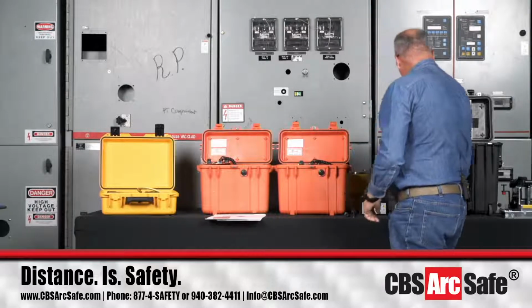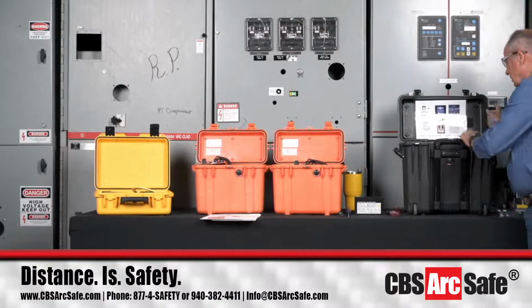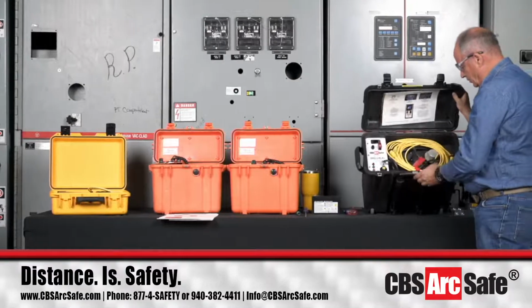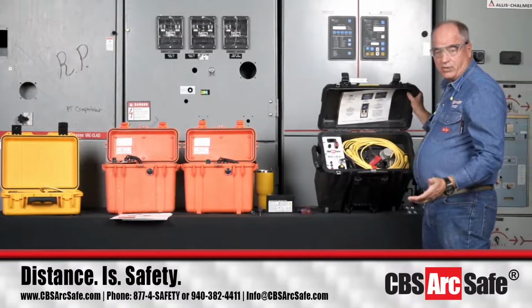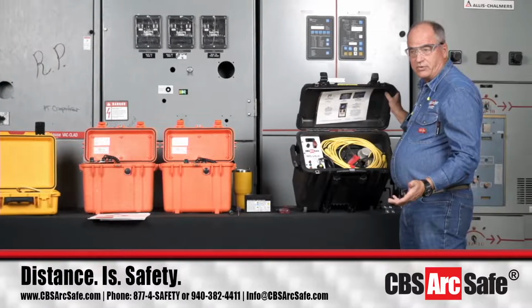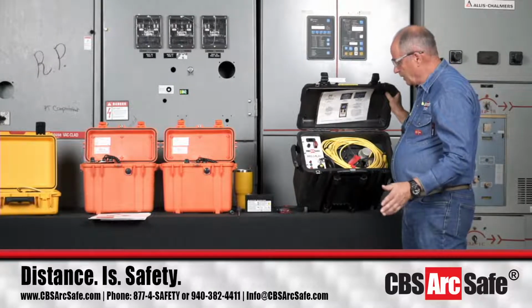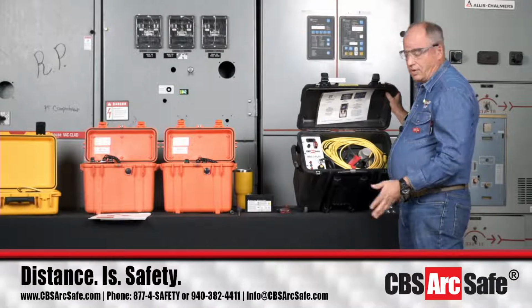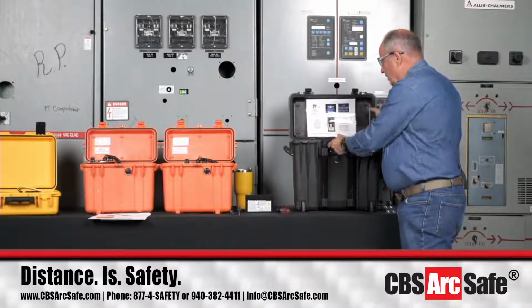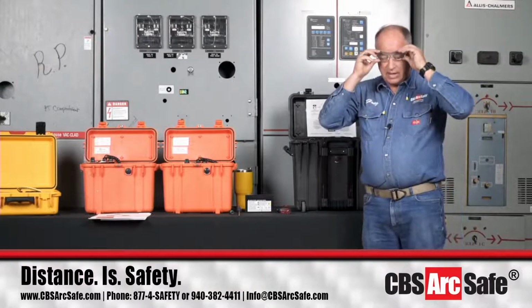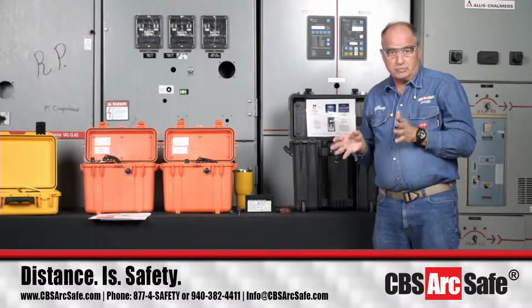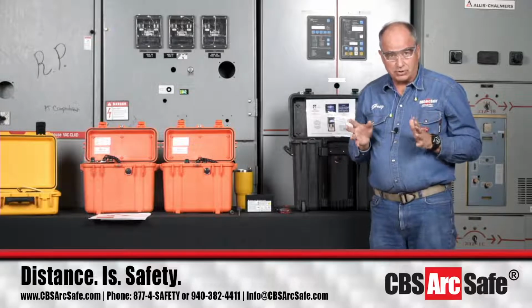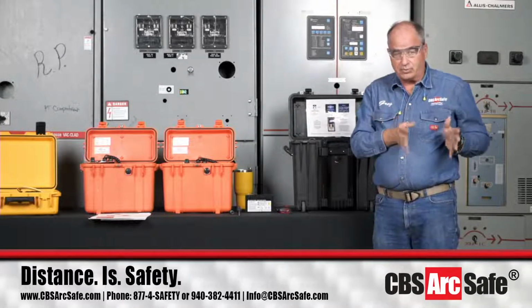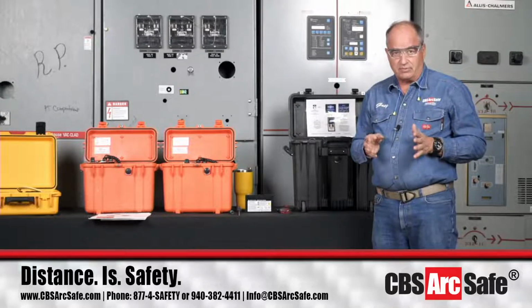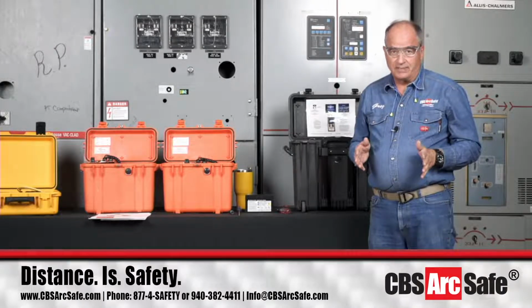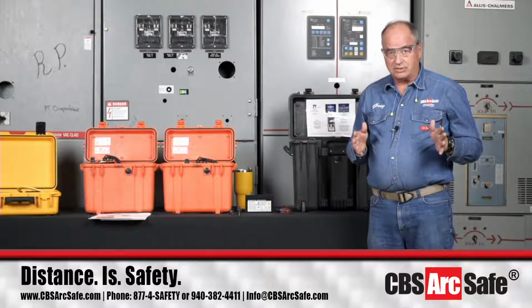With the RS3 DSR line, whether it's an RL, a DSR1, or anything else, this uses a 3.2 amp hour, 12 volt DC battery. These do need to go back to the factory for replacing the batteries. The batteries are supposed to be good for 2 years, and when it goes back to the factory, it's probably about a 2 to 3 day turnaround, because they replace the battery, inspect the unit, and run it through its paces before shipping it back. If they find any problems, they'll give you a call to let you know.